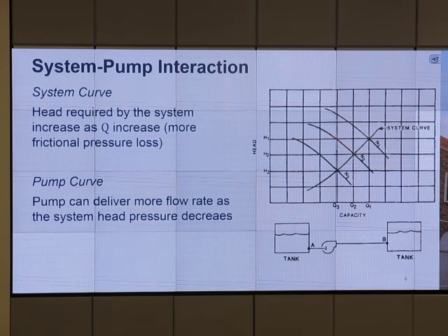So that is the meaning of that pump curve, right? Less head or less restriction, we spin at the same rate, then we flow faster. When you have both curves, the cross point is the operating point. Okay? The cross point is the operating point.